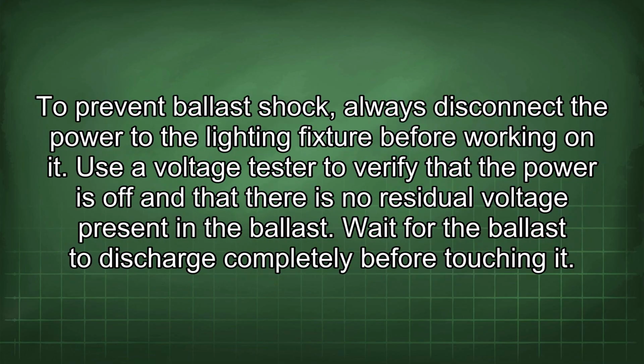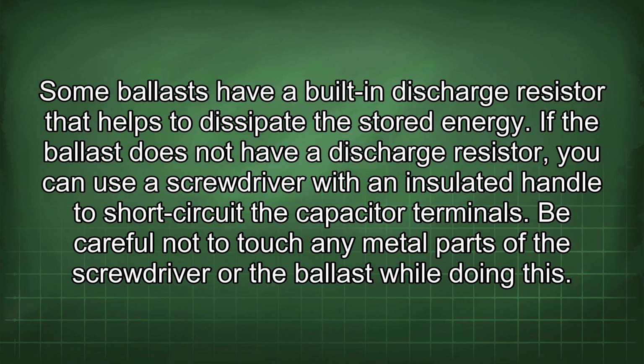To prevent ballast shock, always disconnect the power to the lighting fixture before working on it. Use a voltage tester to verify that the power is off and that there is no residual voltage present in the ballast. Wait for the ballast to discharge completely before touching it. Some ballasts have a built-in discharge resistor that helps to dissipate the stored energy. If the ballast does not have a discharge resistor, you can use a screwdriver with an insulated handle to short-circuit the capacitor terminals. Be careful not to touch any metal parts of the screwdriver or the ballast while doing this.